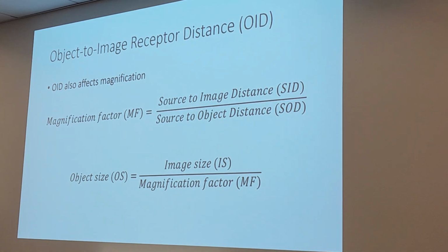That's a great question. We'll see how far we get today. So, if the SID is 72 inches and the SOD is 68 inches, what is the magnification factor? Once again, what is that equation? SID over SOD. Good. Great job.